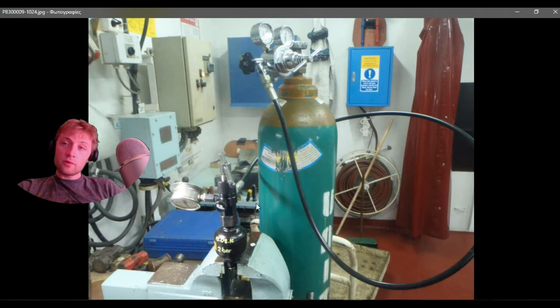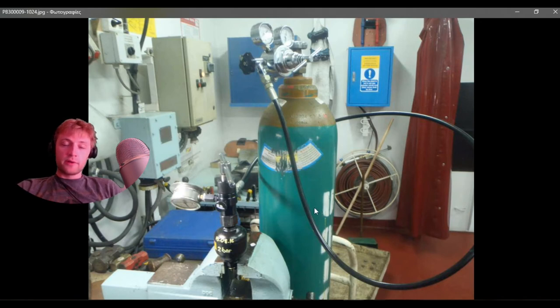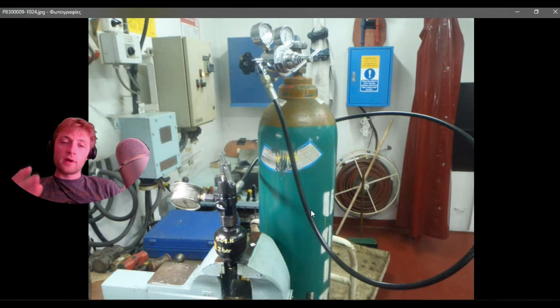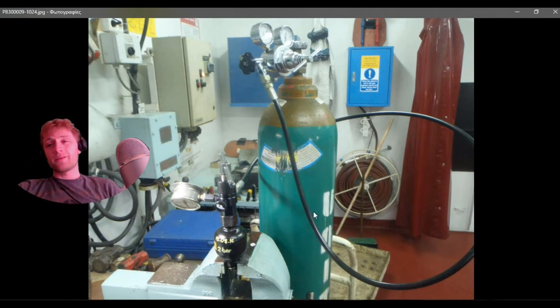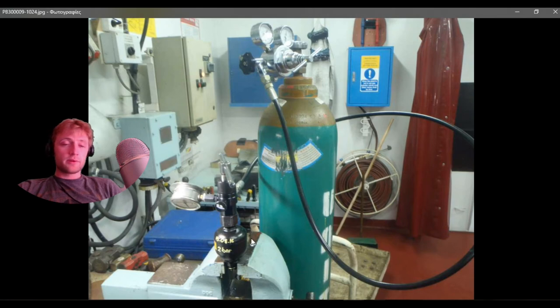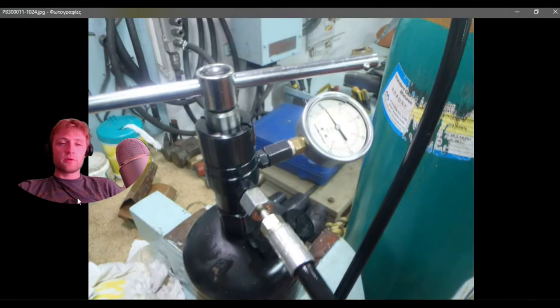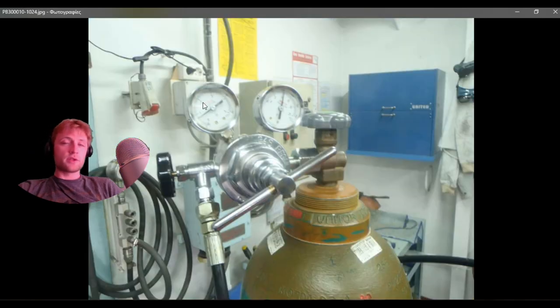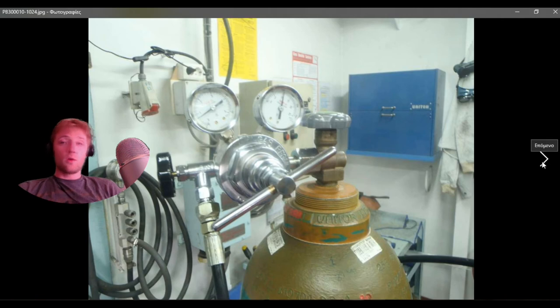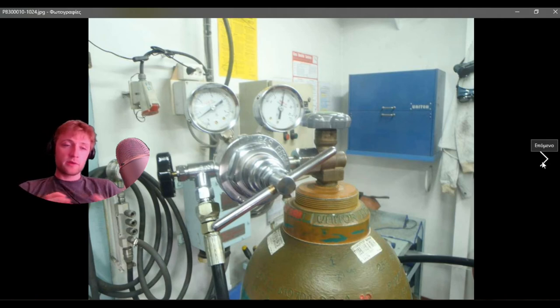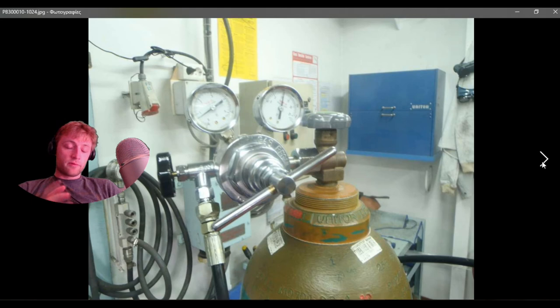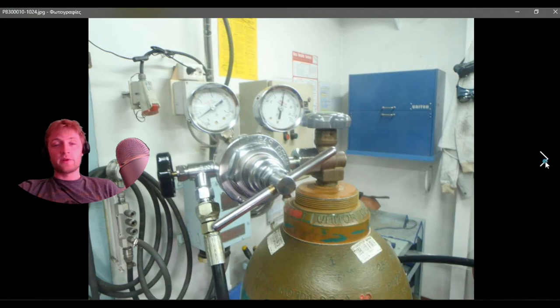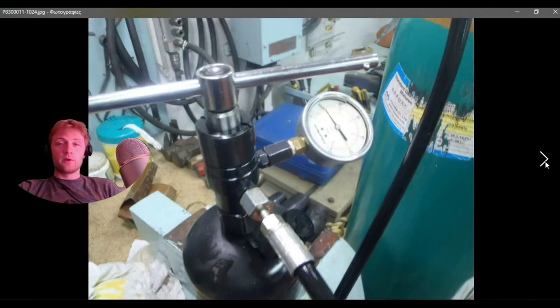Order new accumulators. The same procedure is also for the high pressure accumulator which is 30 bars. The lower one is 2 bars, same exact procedure. The only thing you need to do is adjust the pressure to the higher set point. Always calibrate your gauge before attempting to make any job to have a sure and clear view of what is going on.